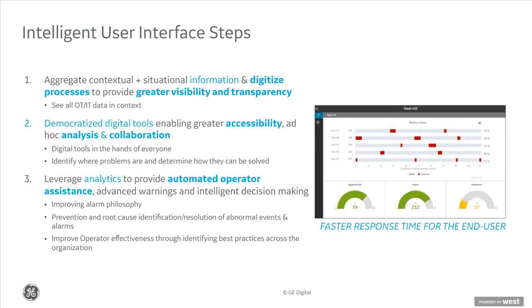And then over time, where that will lead, I believe, truly will be analytics. And I think in regards to analytics, and you hear a lot about it, some of those can be more advanced things, such as having root cause detection of, for example, alarms. It could be a flooding or fleeting alarm. But other things can be just looking at the information that we currently have in our SCADA, such as the high-low limits set for an alarm or for a set point, and if you're going out of it, can you provide notifications to someone to indicate that's happening within your plant operations?